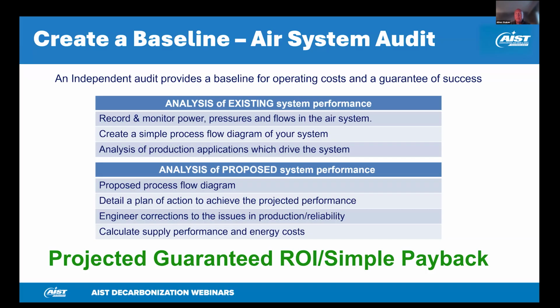And we typically ask, if we failed a compressor today and the pressure started falling, what's the first department that calls? And we want to go spend time with that person in that department to find out why the pressure is so critical in that area. And typically storage or fixing the point of use pressure drop, we can correct that so they're not the first one to call anymore. And part of that effort, we propose a process flow diagram of all the corrective actions. We put a detailed plan of action together with cost and financial impacts, and then we provide a full report to the customer so they can correct those issues and develop a project. And all of our work, when we do this, is projecting a return on investment, and we guarantee that investment based on our findings.